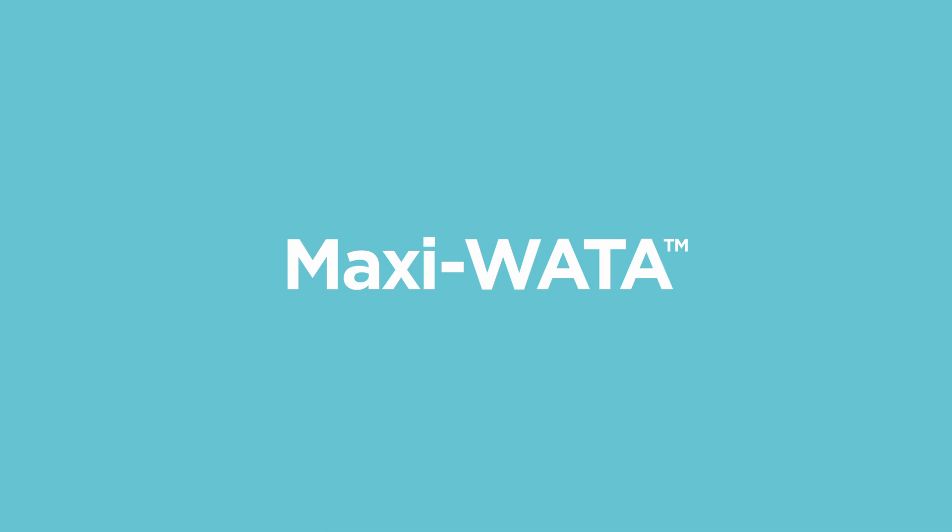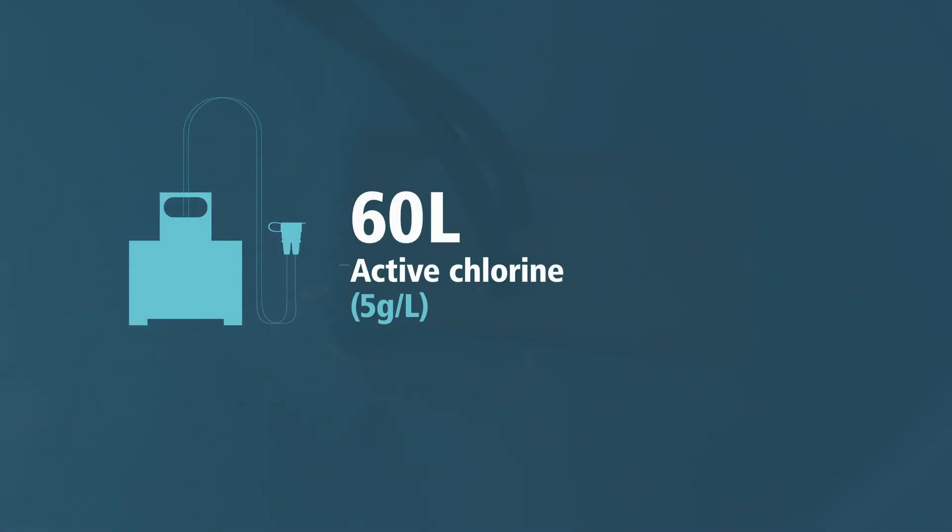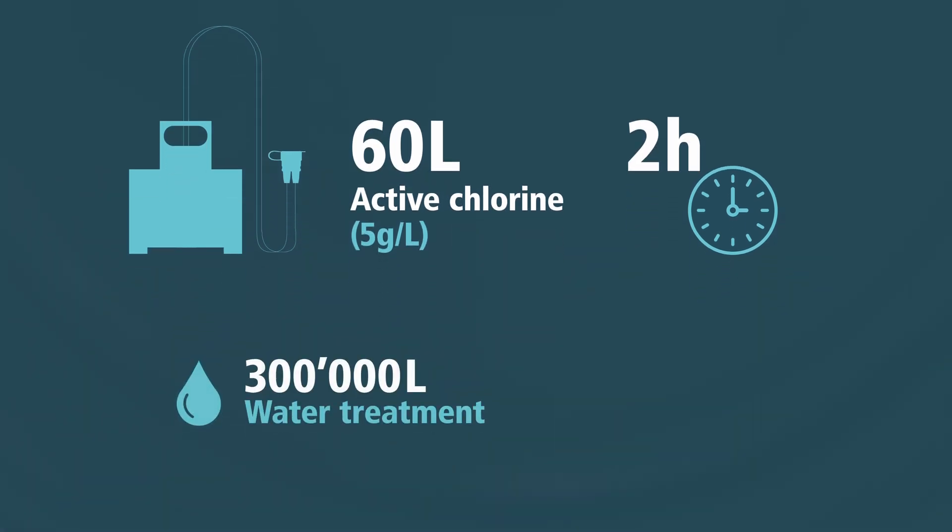WATA technology produces active chlorine useful for water treatment and disinfection. MaxiWater produces 60 litres of sodium hypochlorite solution at 5 grams per litre in 2 hours. One production allows, for example, the treatment of 300,000 litres of water and a production of 150 litres of surface disinfectants.